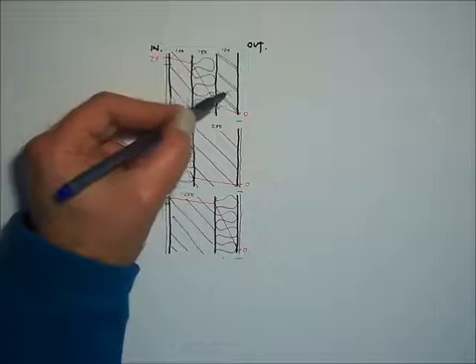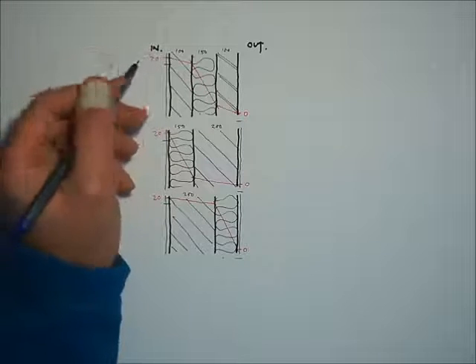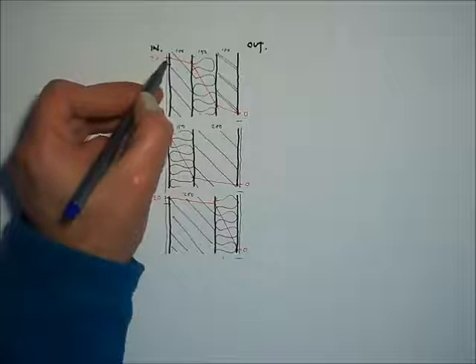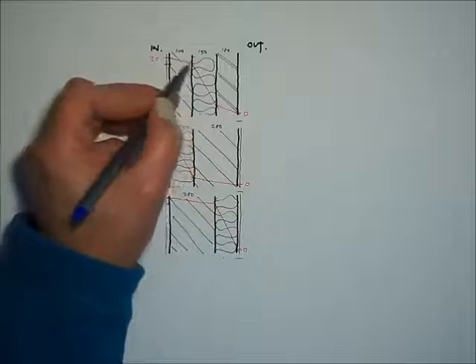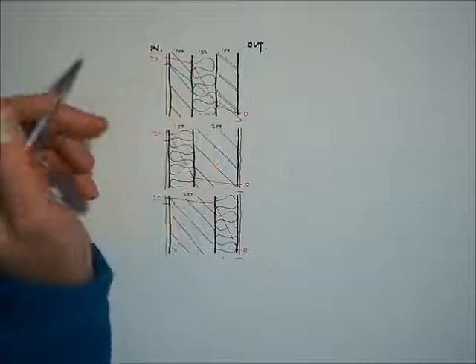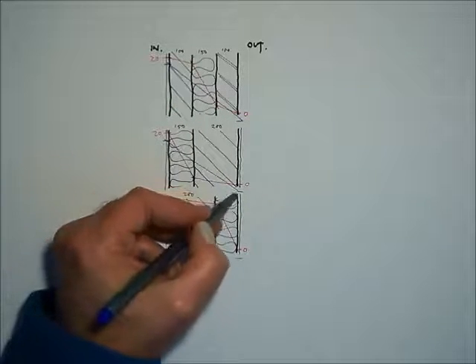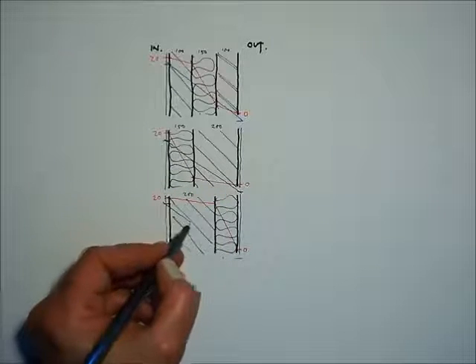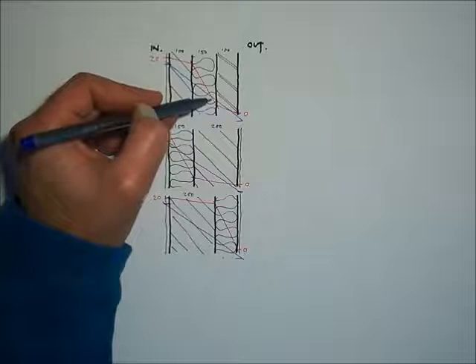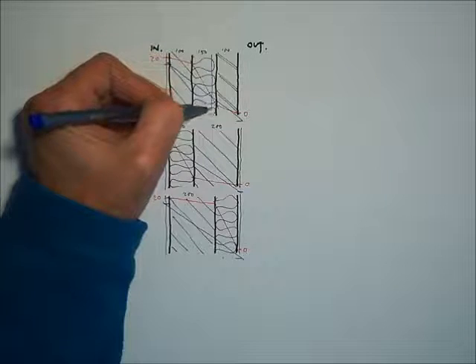Blockwork, mineral fibre and brickwork all have fairly similar resistances to the passage of vapour. Which means, unlike the temperature gradient, which is a zigzag line, there's a straight line, roughly, joining the dew point temperatures. When the dew point temperature is breached by the actual temperature, condensation occurs.